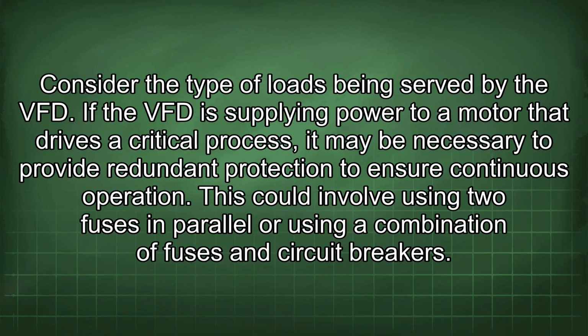Consider the type of loads being served by the VFD. If the VFD is supplying power to a motor that drives a critical process, it may be necessary to provide redundant protection to ensure continuous operation. This could involve using two fuses in parallel or using a combination of fuses and circuit breakers.